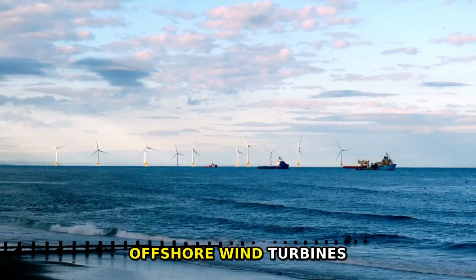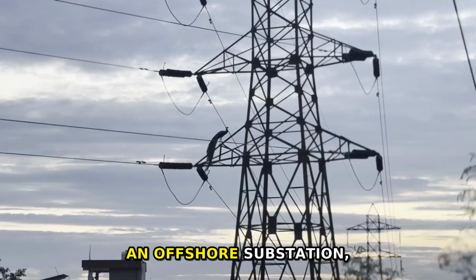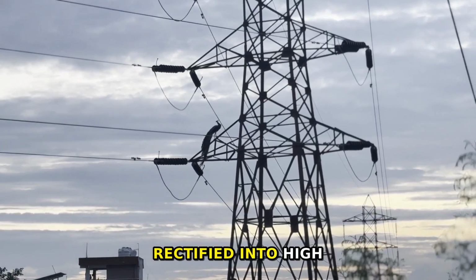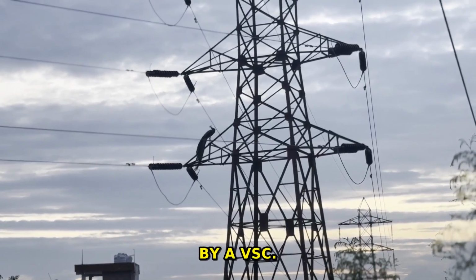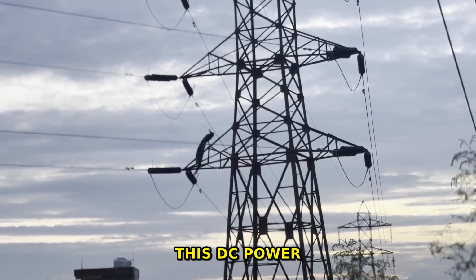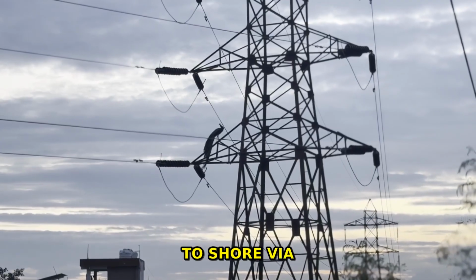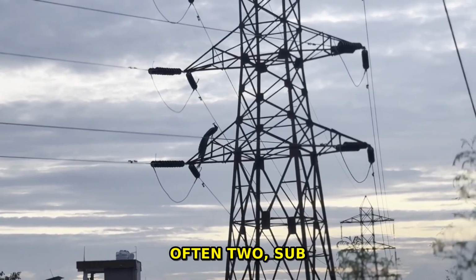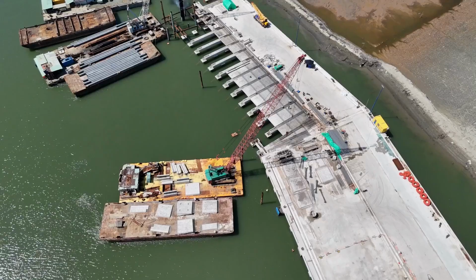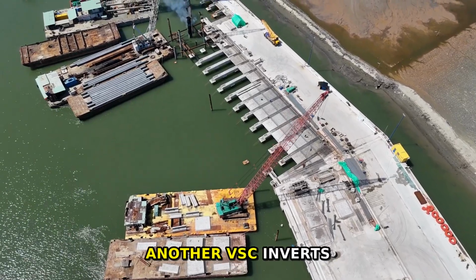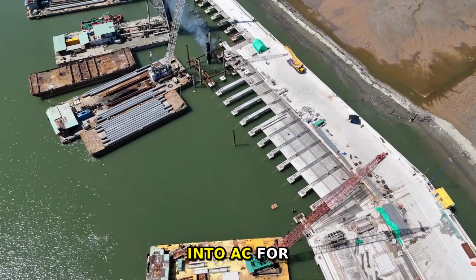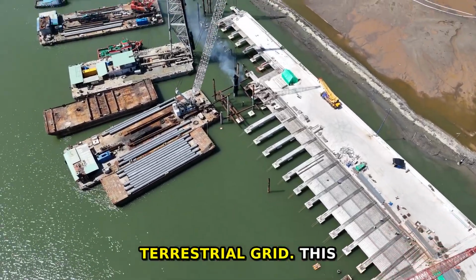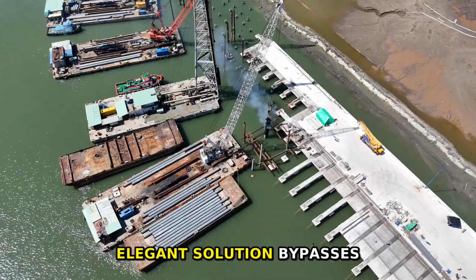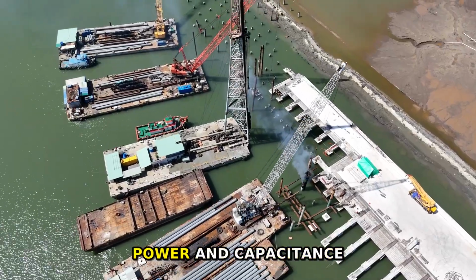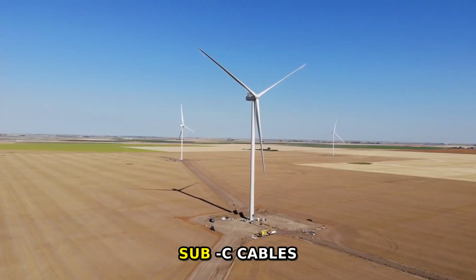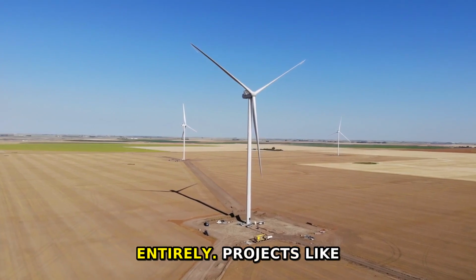Power from the offshore wind turbines is collected by an offshore substation, where it is rectified into high-voltage direct current by a VSC. This DC power is then transmitted to shore via a single, or often two, subsea DC cables. Once on shore, another VSC inverts the DC back into AC for connection to the terrestrial grid. This elegant solution bypasses the crippling reactive power and capacitance issues of AC subsea cables entirely.